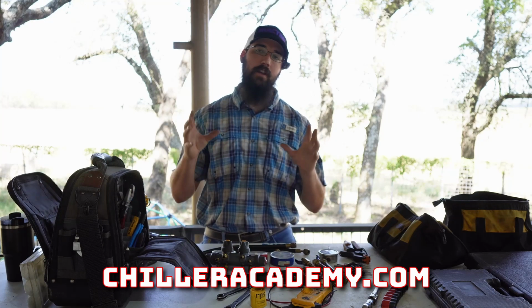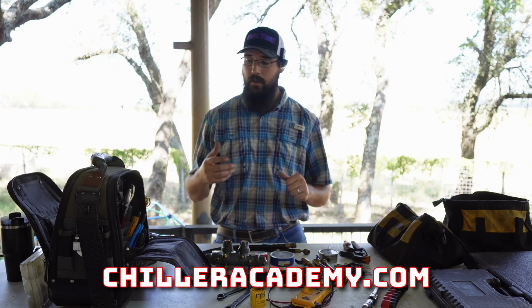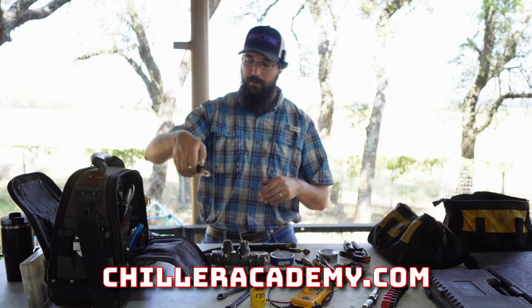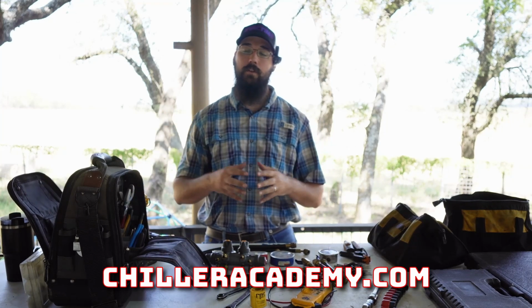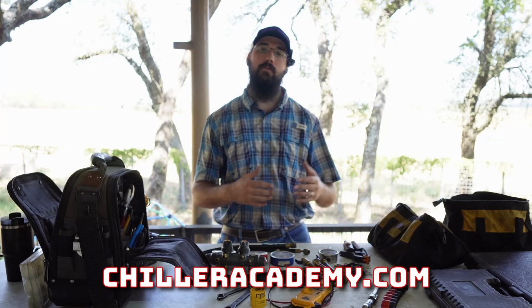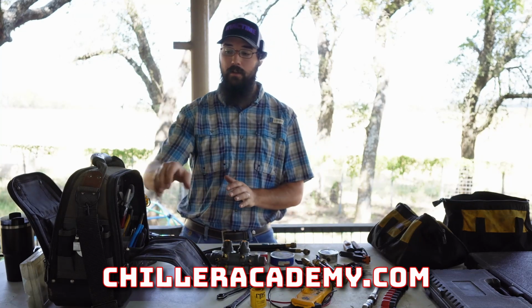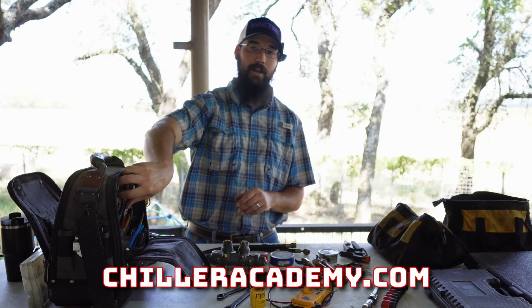Having a set of large gauge crimpers. We're used to having just regular crimpers for standard wire, up to 12 gauge and such. But when we start getting into these aught sizes, 1/0, 2/0, for these compressors and these motors and such, those crimpers aren't going to do it. And I've seen people try to use things like a set of channel locks to do that.